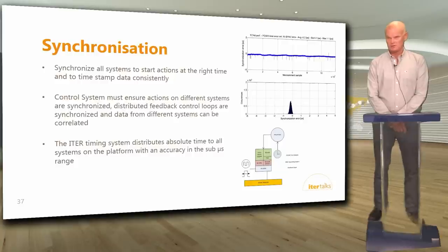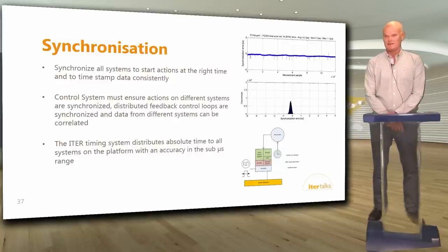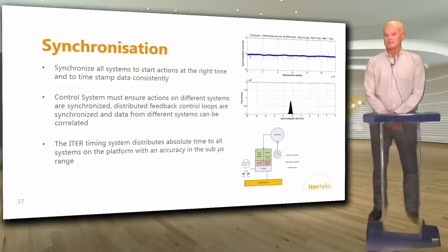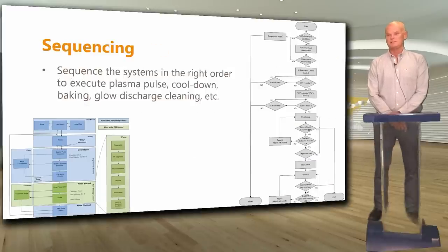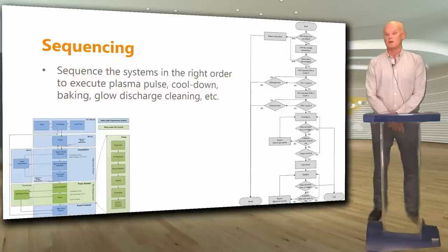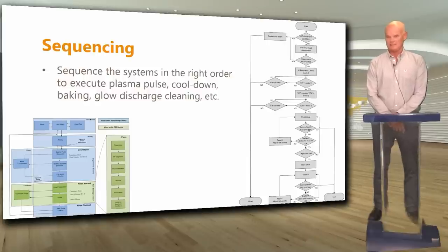Then we need to synchronize things. All systems need to be synchronized so distributed feedback control loops work correctly and data from different systems can be correlated post-mortem. The ITER timing system distributes absolute time to all systems with sub-microsecond accuracy. We also need to sequence things — for example, performing operation tasks like cooldown, baking, glow discharge cleaning, and plasma pulse, which require sequencing different systems in a certain order.